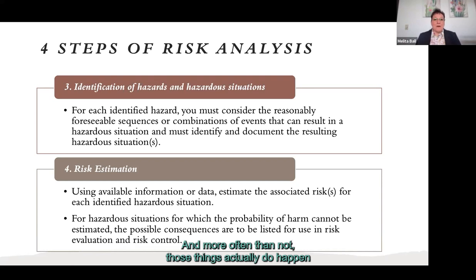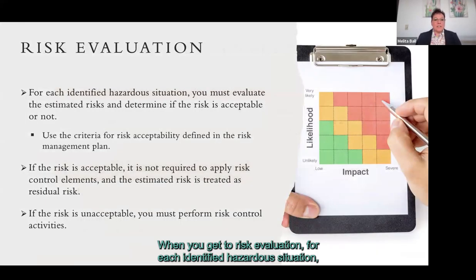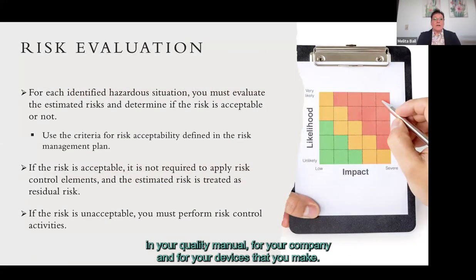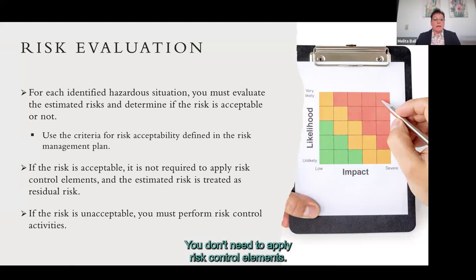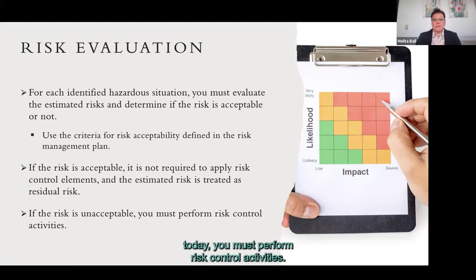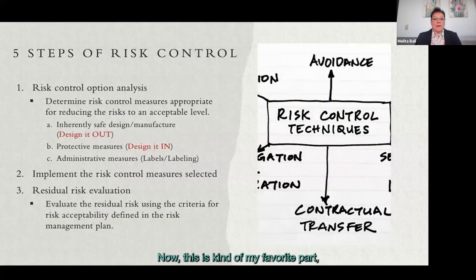During risk estimation, I often tell people to try to think up all the crazy things someone could do with their medical device — more often than not, those things actually happen in real life once the product reaches market. When you get to risk evaluation, for each identified hazardous situation you evaluate the estimated risk and determine whether it's acceptable. Risk acceptability is already defined in your policy and quality manual. If the risk is acceptable, you treat the estimated risk as residual risk and don't need to apply risk control elements.